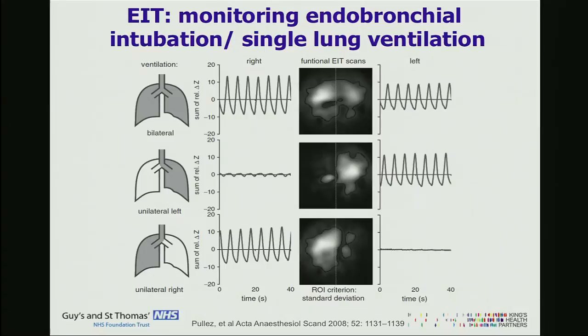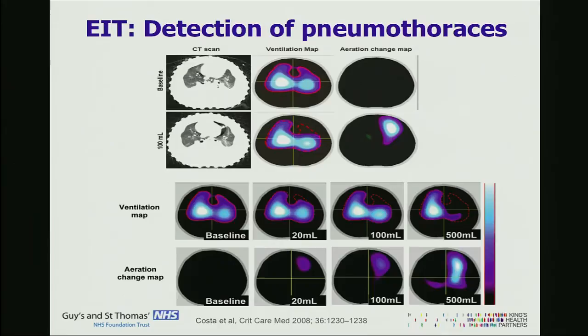We can also detect pneumothoraces in real-time. This is a pig study with a CT scan showing an EIT image of tidal ventilation of that lung. A small pneumothorax was created — 100 millilitres of air inserted in the pleural space — and you can see there is an area missing in ventilation. Subtracting one image from the other gives quantification of the pneumothorax. This can be done in real-time and in this study had 100% sensitivity in detecting a pneumothorax as small as 20 millilitres, providing continuous feedback during high-risk procedures such as central line insertion or recruitment manoeuvres.